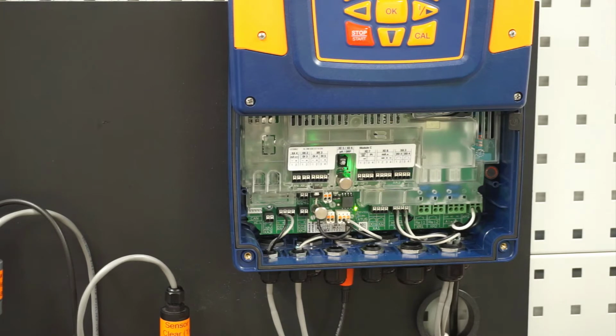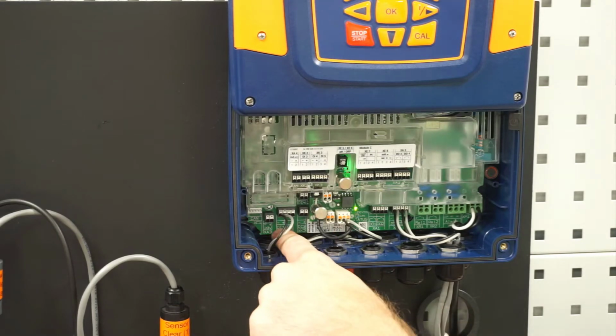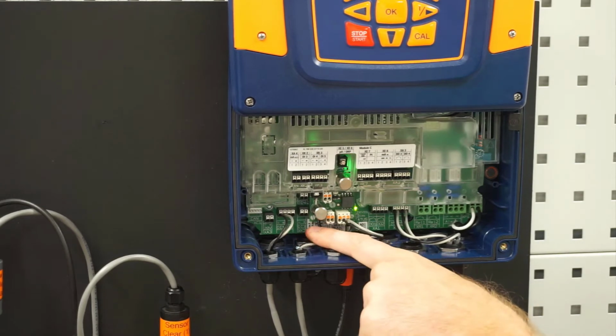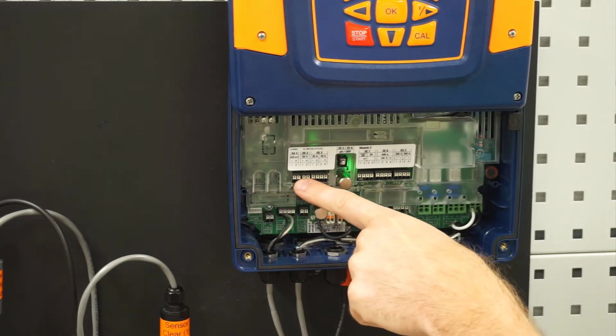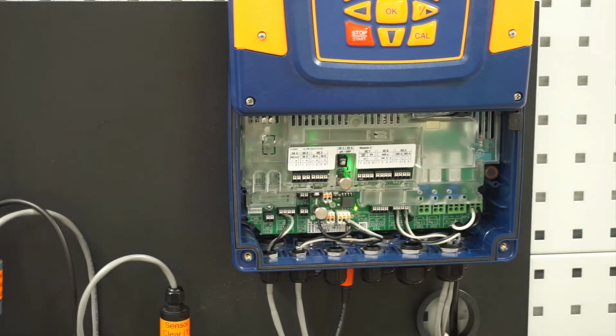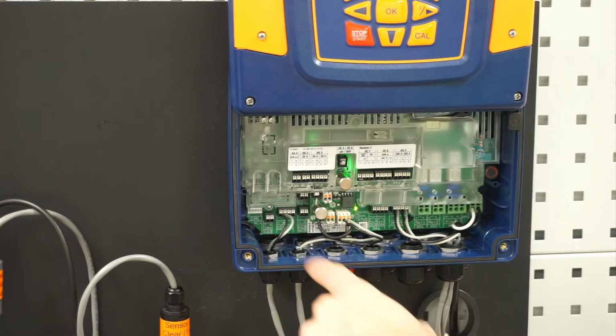That sensor is a go, no-go device, so it's telling me whether or not I have flow or don't have any flow at all. So these digital inputs, you actually have 7 of them. You have DI1, 2, 3, 4, and then up top you have 3 more, so that's a total of 7 digital inputs. They can be used for float switches. They can be used, for instance, for the relay output on one of our ProMinent pumps that just gives us a closure. We could take that into the controller and do what we want with it. We can also bring in a water meter that sends out contacts. That water meter would allow us to do compound loop control, which would give us much tighter control on our process in the injection of chemical. So you do have 7 slots for that.